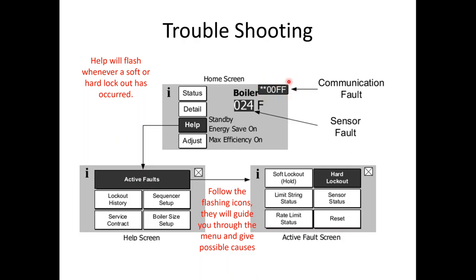This error right here, this **00FF, likes to rear its little head, usually after sharp power disconnects, brownouts, power outages, lightning storms. Again, this control, you're going to want to treat it kind of like you would your computer. There's 3 microprocessors inside of that Sage control. Dirty voltage fluctuations, they're not a big fan of it. It's not a non-negotiable standard, but it is advised to protect the unit with a UPS, some sort of an uninterruptible power supply, or a surge protector. Definitely, especially in some of the rural areas.